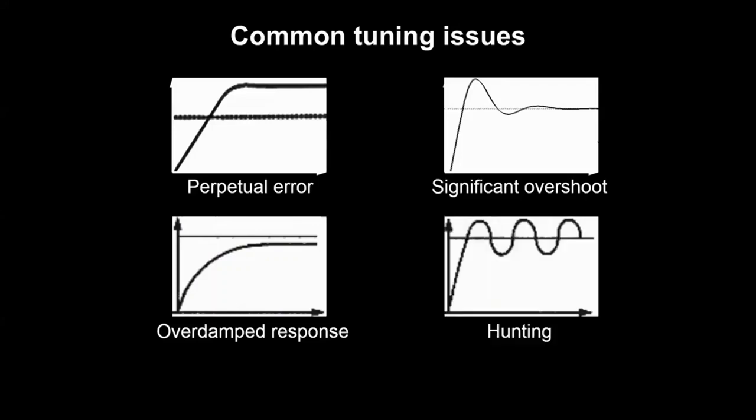If you can ever imagine looking at something like an economizer damper, where it appears that damper is just closing, opening, closing, opening, and by the time it realizes it's overshot one end of the set point, it's shooting back to the other one. We would call that hunting, and that's something that tuning can address.